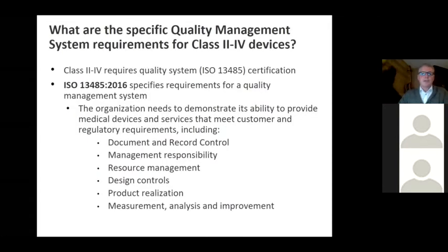So with respect to the quality management system, what are those requirements? Well, ISO 13485 specifies requirements for your QMS, or your quality management system. Any organization that is going to be designing or manufacturing medical devices needs to demonstrate its ability to provide those devices and the services associated with those devices that will consistently meet the customer and regulatory requirements.